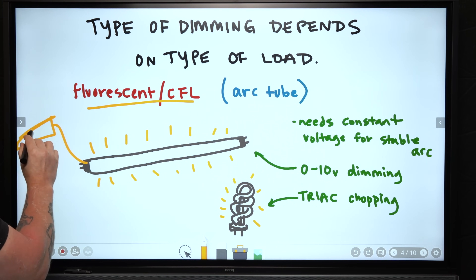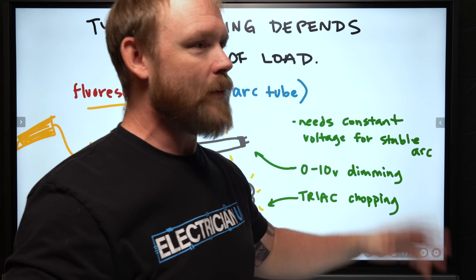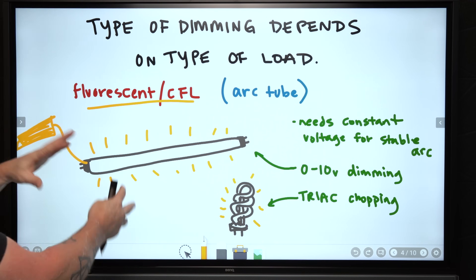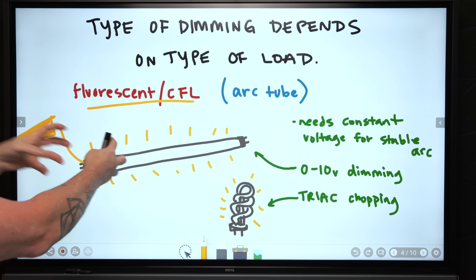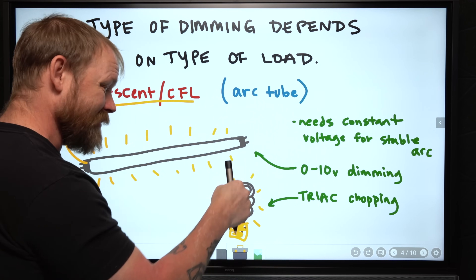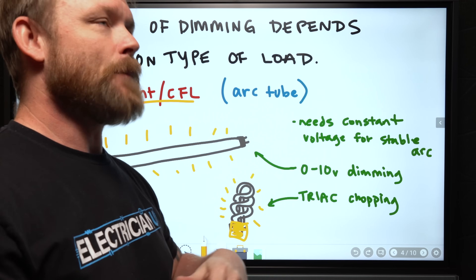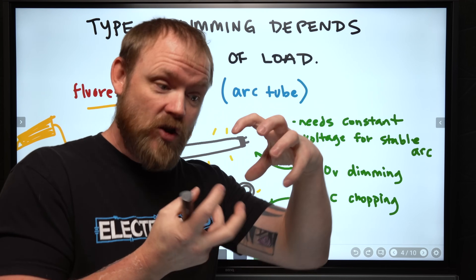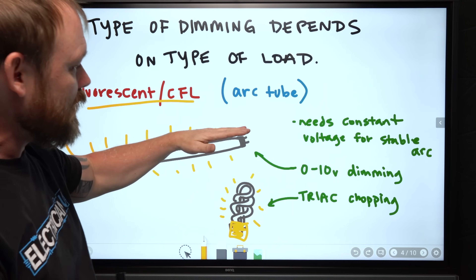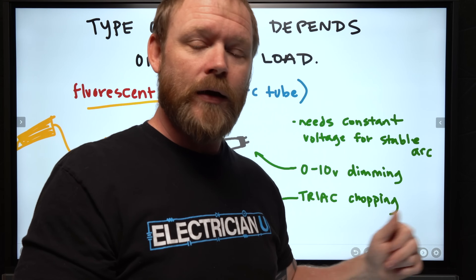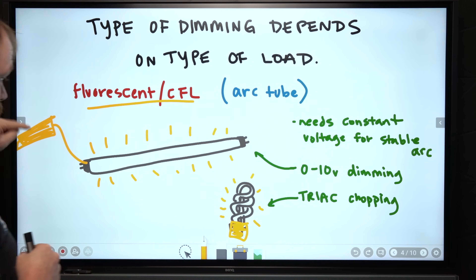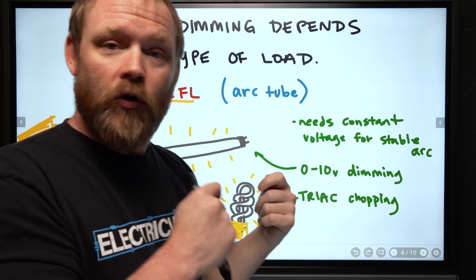With typical fluorescents, you usually have some kind of external ballast - a rapid start ballast, two-lamp or four-lamp - usually an electronic ballast, though old magnetic ballasts work similarly. Many CFLs are self-ballasted, meaning ballast technology is integrated into the lamp itself. Others have externally operable ballasts. Typically with fluorescent, we deal with zero-to-10-volt dimming, which means we can't change the current or voltage from the power source powering the lamp, because it needs a stable current to keep the lamp glowing.